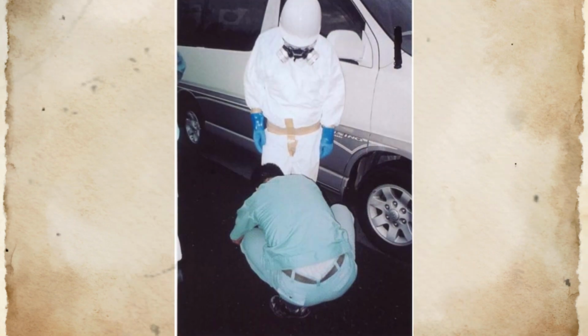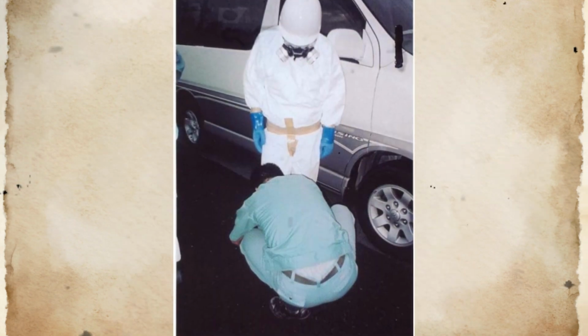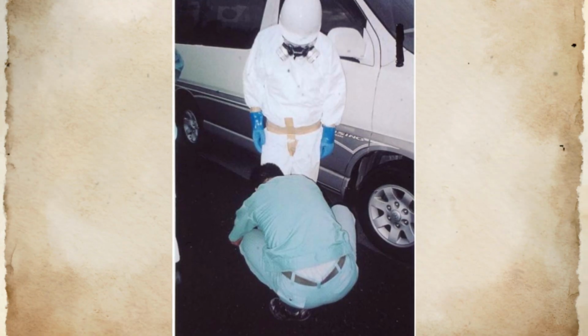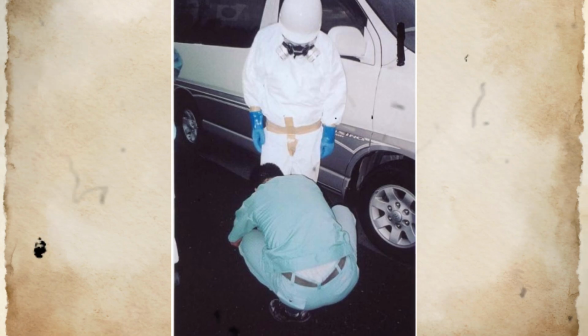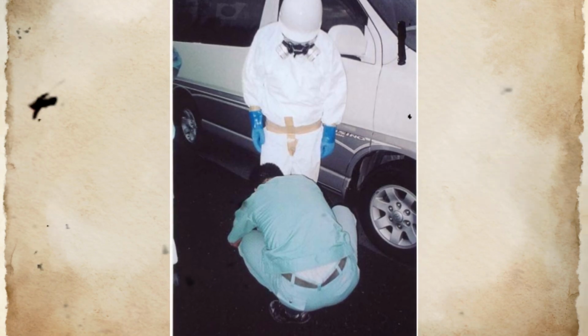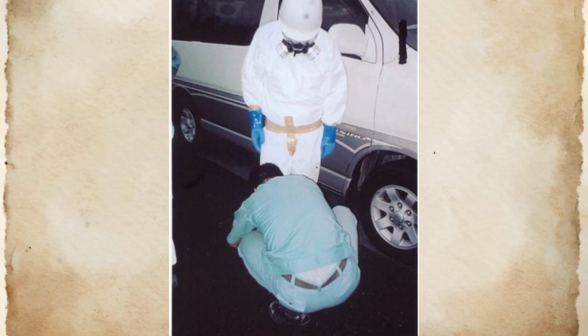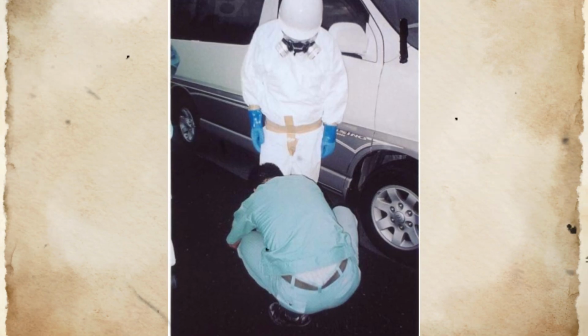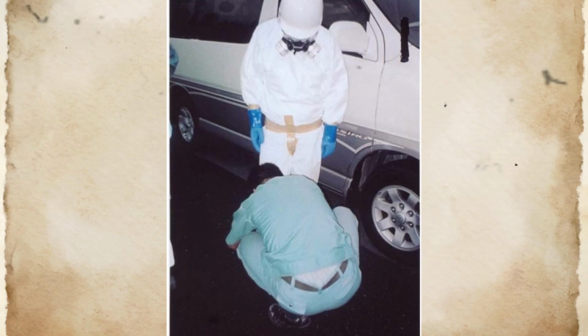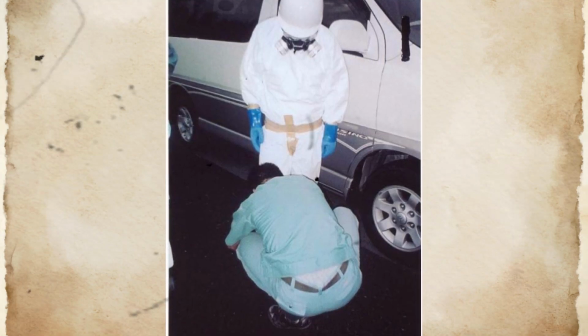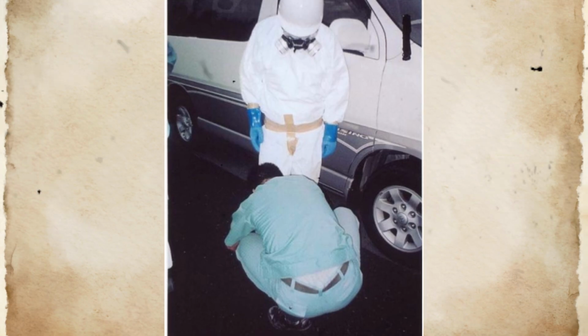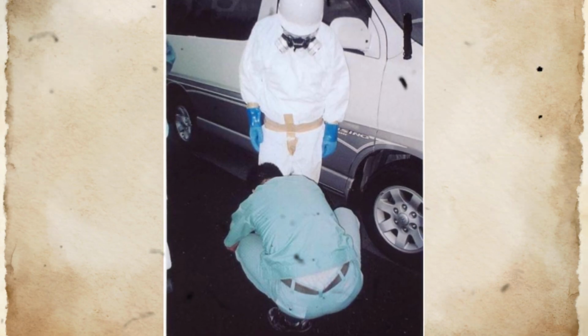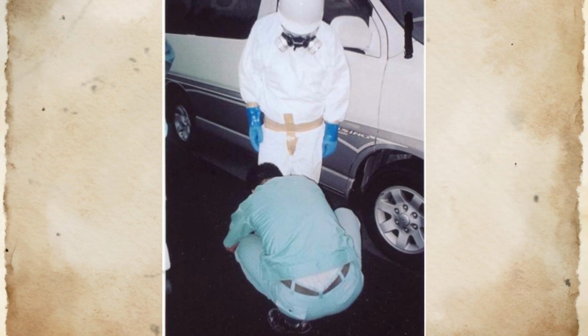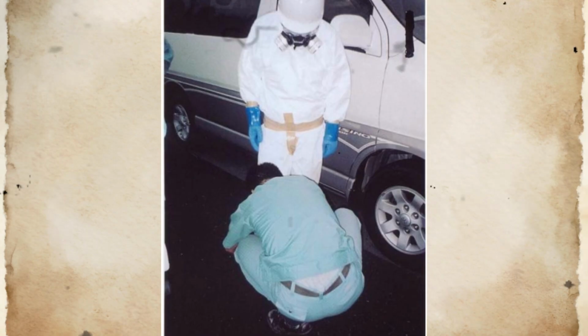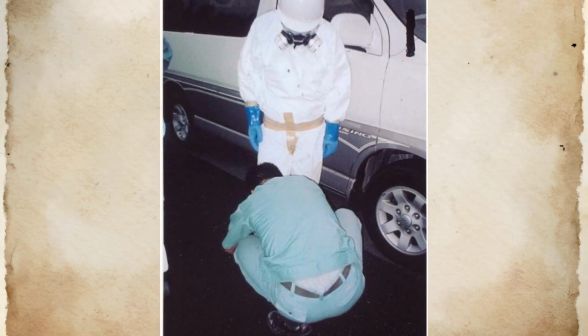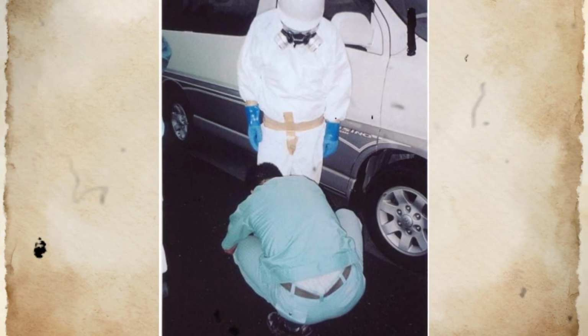Station blackout as a design condition had been considered during the reactor's licensing, but as a brief interruption, not a sustained state. The Regulatory Guide for Reviewing Safety Design of Light Water Nuclear Power Plants, established in 1977, required nuclear facilities to ensure the safe shutdown and subsequent cooling of reactors in the event of a short-term station blackout, at least 30 minutes. This guideline reflected the prevailing wisdom that Japan's reliable electrical grid and robust emergency power systems made extended blackouts extremely unlikely. The assumption proved false not because it was unreasonable, but because it was incomplete.